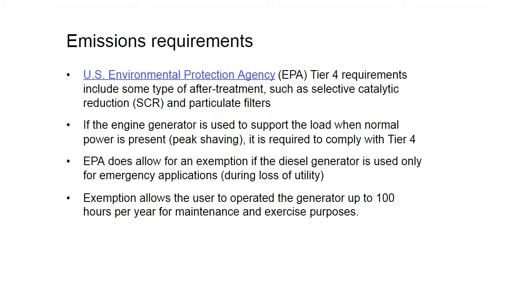If it's only used for emergency applications, then they are not required to meet Tier 4. There is one exemption that allows you to operate the generator for 100 hours for maintenance and still fall under the Tier 4. A lot of data centers or mission-critical facilities like to do maintenance of UPS systems and certain other systems on generator. So that's something when you get into design to really figure out how much time they're going to be using for maintenance, because if it goes over that 100 hours a year, it will be required to have SCRs, and you just want to make sure that you have the space and the capabilities to add that, or if you need to, in the design.